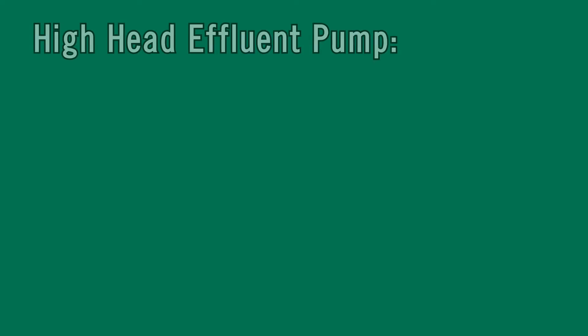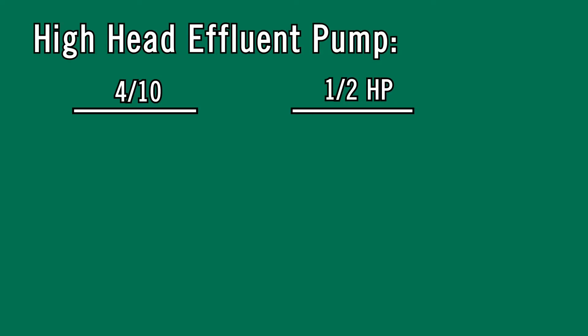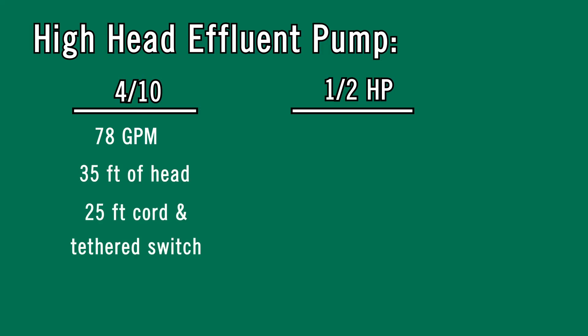The high head effluent pump comes in a four-tenths and a half horsepower. The four-tenths will produce 78 gallons per minute and will reach 35 feet of head. This comes with a 25-foot cord and tethered switch.